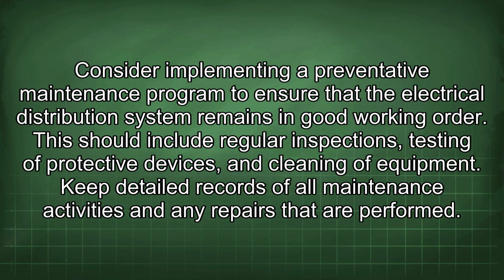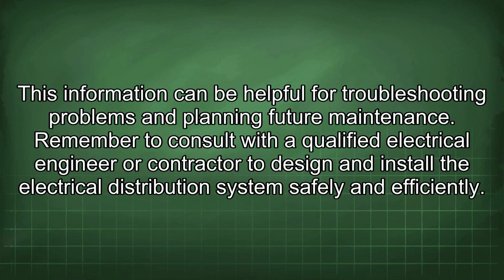Consider implementing a preventative maintenance program to ensure that the electrical distribution system remains in good working order. This should include regular inspections, testing of protective devices, and cleaning of equipment. Keep detailed records of all maintenance activities and any repairs that are performed. This information can be helpful for troubleshooting problems and planning future maintenance.